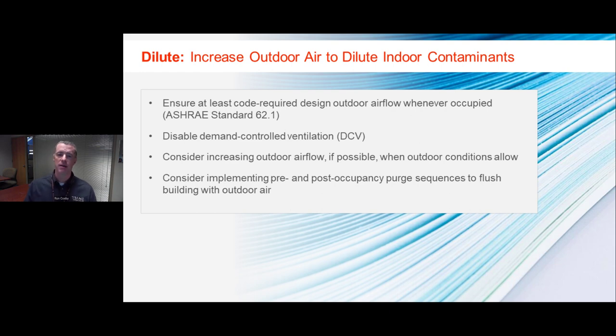And then finally, depending upon the capabilities of your system and your controls, you can implement pre or post purge occupancy sequences that can help flush that indoor space either at the end of the day or prior to the beginning of the day, so that if you have any potential contaminants in the space, you can get rid of them prior to the next shift, prior to the next occupancy level.